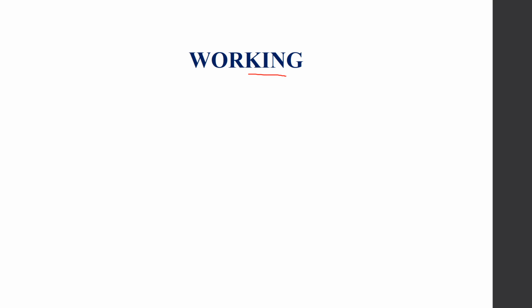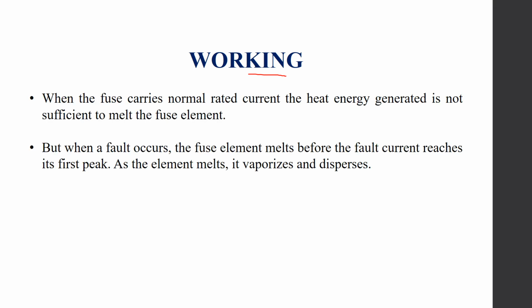Working of an HRC fuse is quite similar to that of an ordinary fuse. That is, when the fuse carries the normal rated current, the heat so produced is not sufficient to melt the wire. Whereas, when a fault occurs or when the current exceeds the predetermined value, then the fuse wire melts. As the fuse wire melts, it vaporizes and disperses. But there is a possibility of arc reformation, and therefore in an HRC fuse the arc quenching medium forms a chemical reaction with the metal vapor, thus forming a high resistance substance which helps the arc to quench, and therefore the current is interrupted.